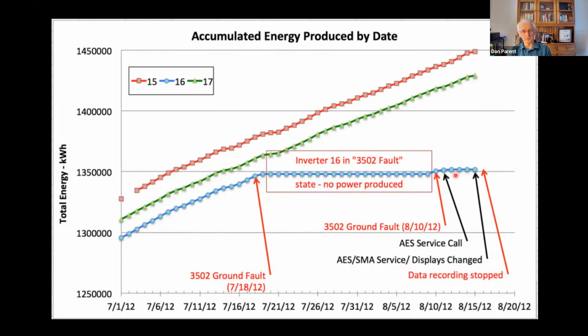The incident occurred in 2013. It's approximately a year after what you see here on the screen. And lo and behold, what you see here on the screen is relatively close to what happened just before the incident. There was a 3502 fault that happened approximately 2 or 3 hours before the fire started. So the fire must have been percolating up there for a period of time. And then shortly after that, inverters 15 and 17 were shut down, again for faults that they experienced as a result of the fire.